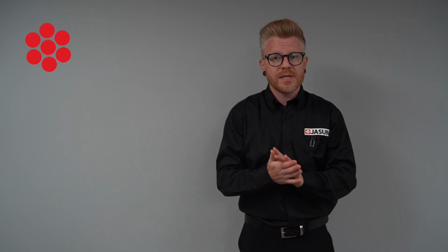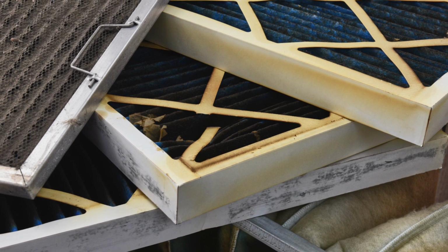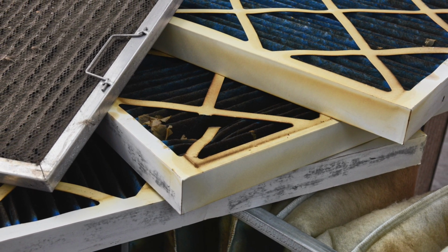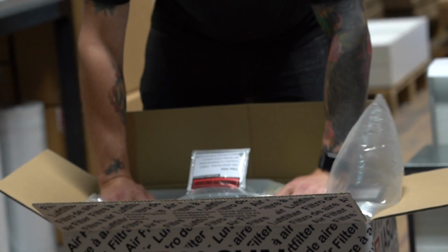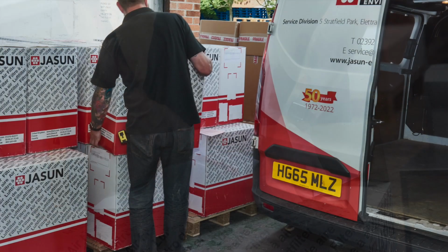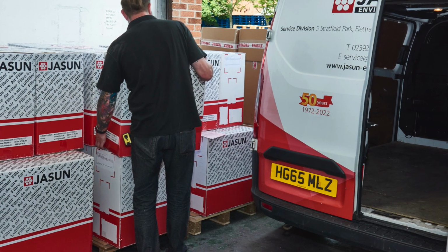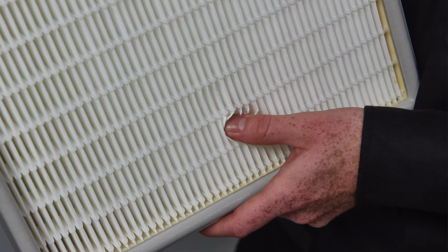A blinded or heavily soiled filter will also eventually reduce the airflow and should be visually checked regularly for condition and that it's free of damage. Filters should be dry stored securely indoors in their original packaging, ideally on pallets. Great care should be taken to ensure that they are not damaged and don't come into contact with chemicals or water.